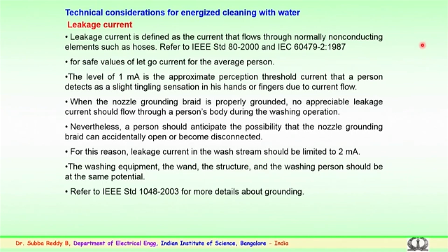These details of the leakage current and the particular information are described in the IEEE standard and IEC standard as mentioned, where it gives the minimum values of the leakage current for the hoses and the equipment which is being used for the cleaning for energized conditions. So, for safe values the let go current for an average person also is to be considered.